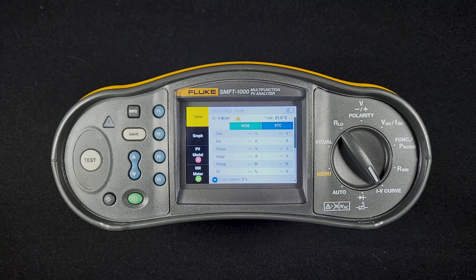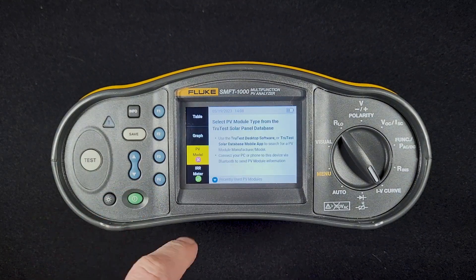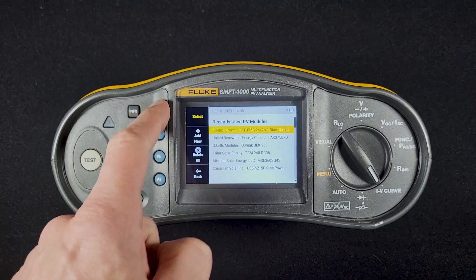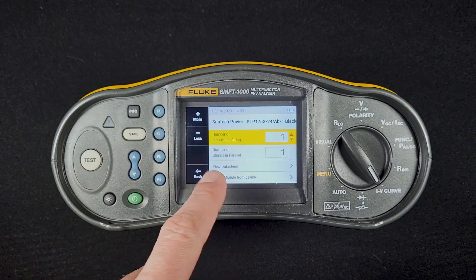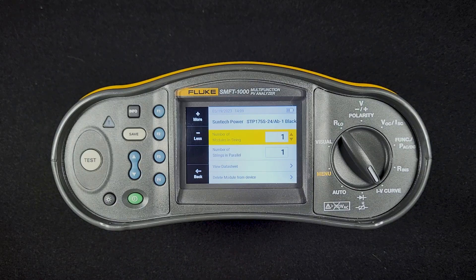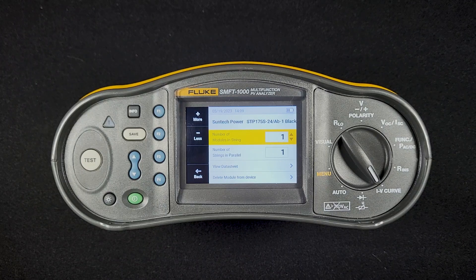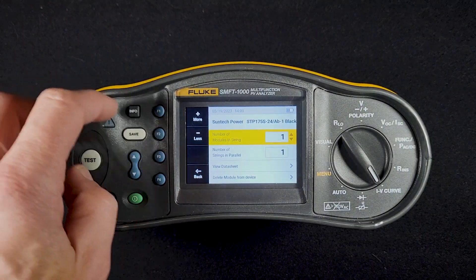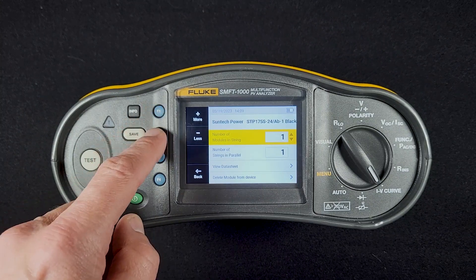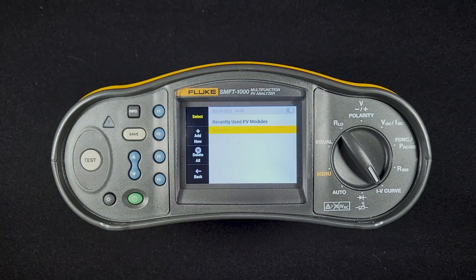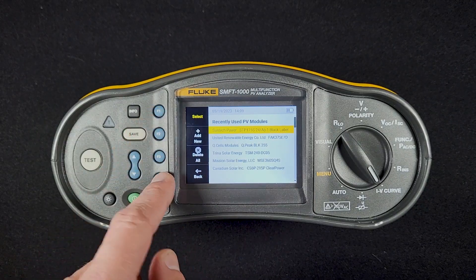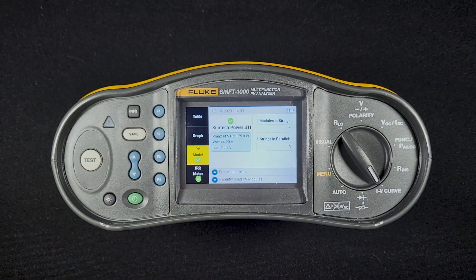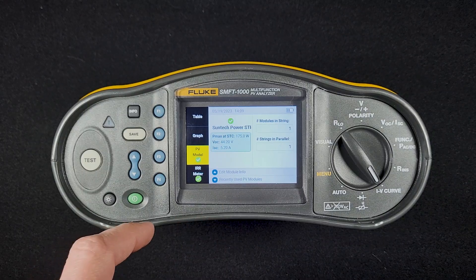Once I'm ready to create a test, I would want to select a PV module first. So I'm going to select a module — I'll just take the one at the top of the list. I'm going to tell it how many modules I have in the string and how many in parallel. The SMFT-1000 can measure up to 1000 volts, which corresponds to the number of modules in a string, and it can measure up to 20 amps, which is the number in parallel. You hit the F1 and F2 buttons to increase or decrease that number. Once I have that entered in, you can see the PV module is now checked, my IRR meter is connected, and I am ready to test.